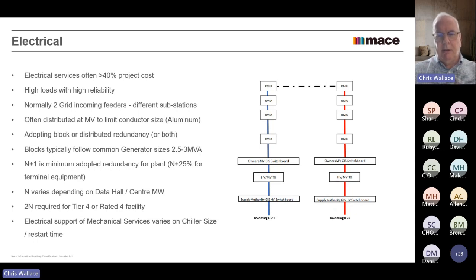When you're getting above about 30 MVA, you're probably going to go to a high voltage power supply, and depending on where you are in the region, it'll be different voltages. So I won't quote voltages, different countries, different things. But quite often what they do is come in at high voltage and then drop down through transformers. You obviously have a local supply authority high voltage switchboard. You might have an owner's high voltage switchboard as well, depending on the situation. Then you'll drop down through a transformer to owner's medium voltage switchgear.